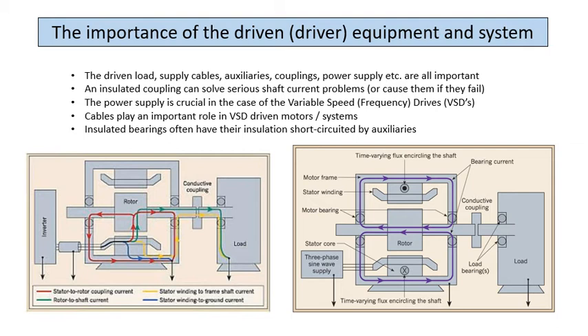The one thing I'll show you later is this 850 kilowatt installation. It ran perfectly for 7 years. So that's an EX environment, VSD driven, 850 kilowatt machine. It ran perfectly for 7 years, came out for a standard overhaul, had the bearings replaced, and went back into service. 3 months later it got taken out and it had not as severe fluting as I showed you earlier, but pretty much unacceptable fluting. And the reason we found was that the coupling guard was touching the part of the end shield that should have been insulated.